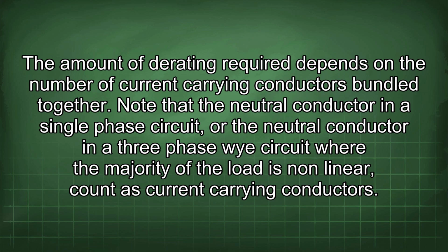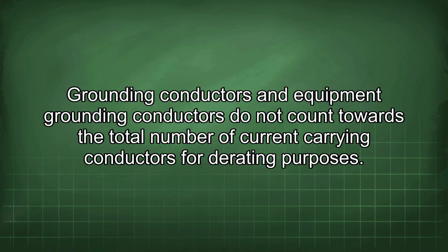Note that the neutral conductor in a single-phase circuit, or the neutral conductor in a three-phase Y circuit where the majority of the load is nonlinear, count as current-carrying conductors. Grounding conductors and equipment grounding conductors do not count towards the total number of current-carrying conductors for derating purposes.